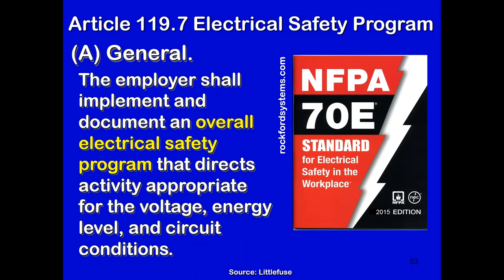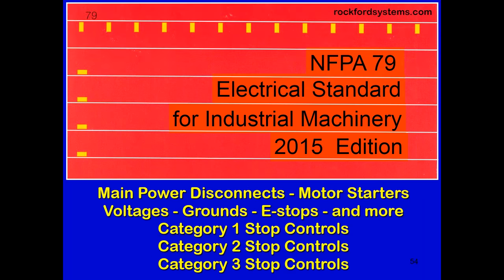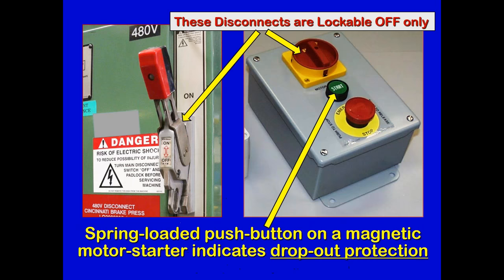Which is not to be confused with NFPA 70E that contains the arc flash issues for people that have to work on energized panels and have a certain amount of protective equipment in order to do that. So actually, your electrical and maintenance people should have both the NFPA 70E and NFPA 79. So 79 contains things like the rules for main power disconnects, motor starters, voltage reduction using step-down transformers, properly grounded circuits, emergency stops, and three different categories of motor stop controls.